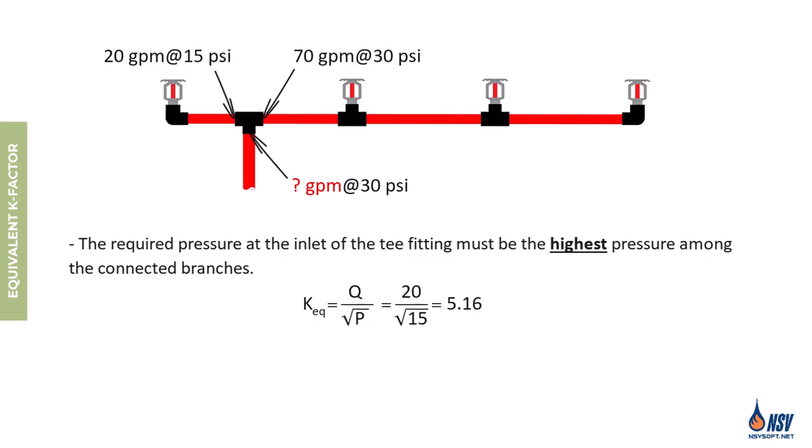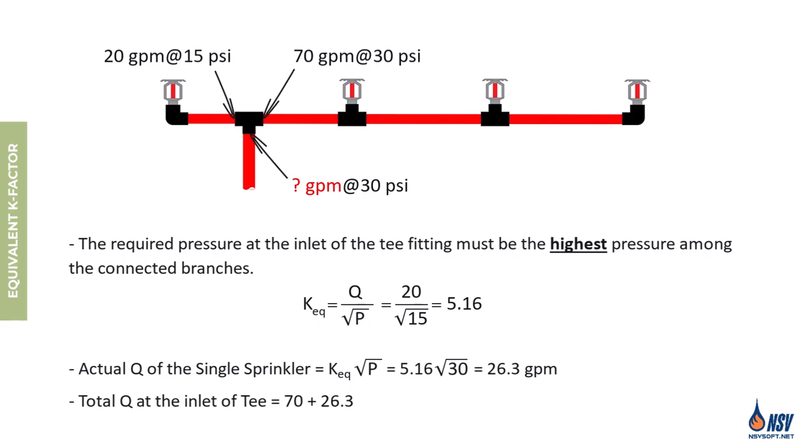Now that we've determined the equivalent K factor of that section and we're supplying 30 psi at the tee inlet, the actual flow rate of the single sprinkler will be approximately 26.3 gallons per minute. This means the sprinkler will discharge more than the originally required 20 gpm due to the higher supplied pressure. Therefore, the total required flow rate at the inlet of the tee is 70 + 26.3 = 96.3 gallons per minute.